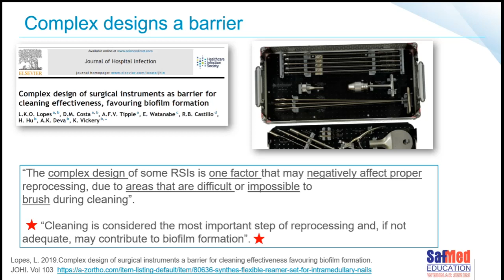We know that the complex design of some of these reusable surgical instruments is one of the factors that may negatively affect proper reprocessing, because it's damn difficult, if not impossible, to brush during the cleaning process. If you don't do all of this, there is a chance that it can contribute to biofilm formation. We also know that once biofilms form on a surgical instrument, they can be very difficult to detect and extremely hard to remove. So what was their finding after repeating this process 20 times?